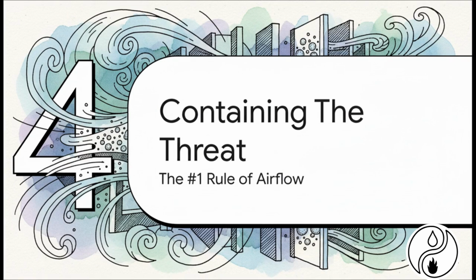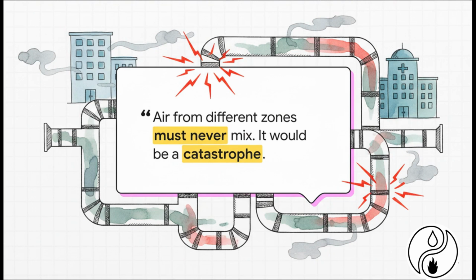All of this—the temperature, the humidity, the pressure—leads to one of the most unbreakable rules in hospital design: containing the threat by controlling airflow. This is the absolute red line. In an office building, air might circulate all over the place. In a hospital, that would be a disaster. Air from different critical zones can absolutely never, ever mix.